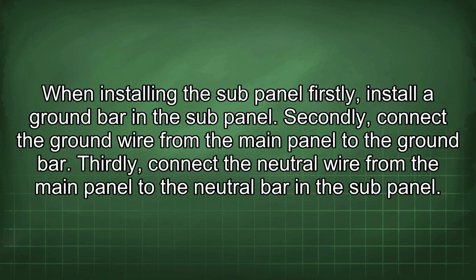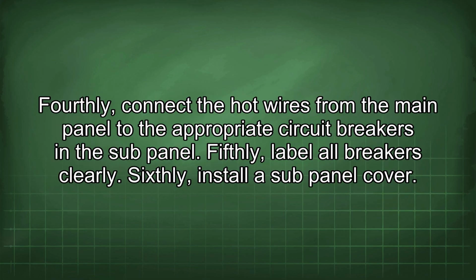When installing the sub-panel, firstly, install a ground bar in the sub-panel. Secondly, connect the ground wire from the main panel to the ground bar. Thirdly, connect the neutral wire from the main panel to the neutral bar in the sub-panel. Fourthly, connect the hot wires from the main panel to the appropriate circuit breakers in the sub-panel. Fifthly, label all breakers clearly. Sixthly, install a sub-panel cover.